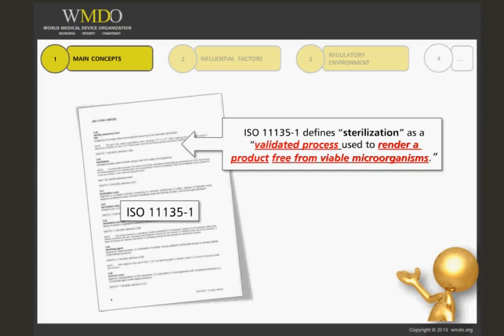Of course, during routine sterilization, you cannot test each device for sterility. You have to find alternative ways to guarantee sterility while still ensuring scientific evidence that your process is able to consistently deliver the same results.